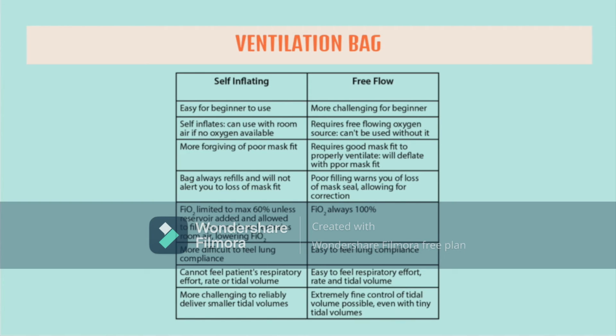FiO2 is always at 100%. It is also easy to feel lung compliance. Also easy to feel respiratory effort, rate, and tidal volume. Lastly, extremely fine control of tidal volume is possible, even with tiny tidal volumes.